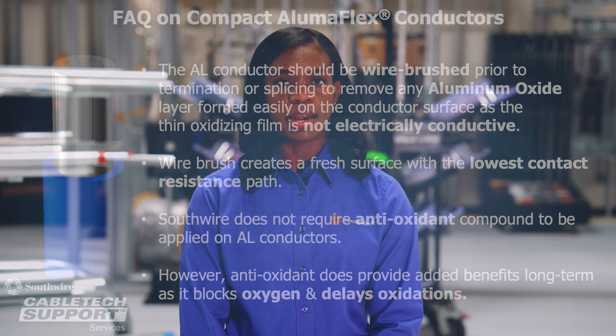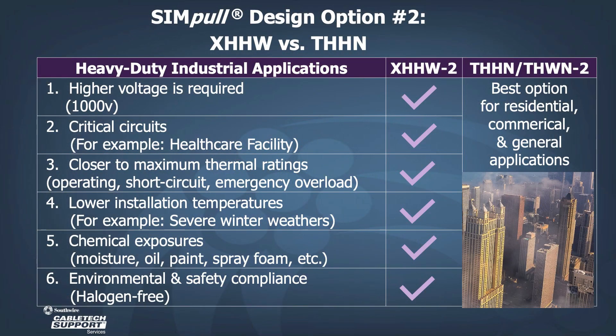Our second design option is whether to choose SIMpull XHHW-2 or SIMpull THHN. THHN-THWN-2 is the best option for residential, commercial, and general applications. However, if your application requires a higher voltage, is a critical circuit, closer to the maximum thermal ratings, lower installation temperatures, potential chemical exposure, or you need a halogen-free product, XHHW-2 is more suitable.